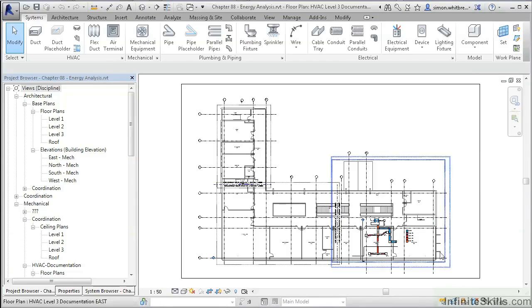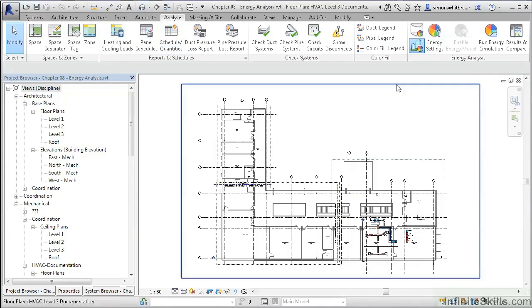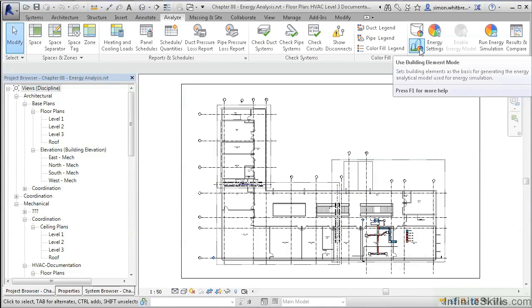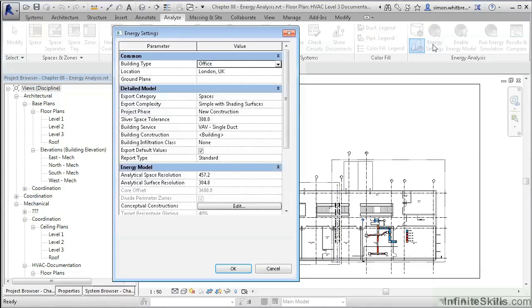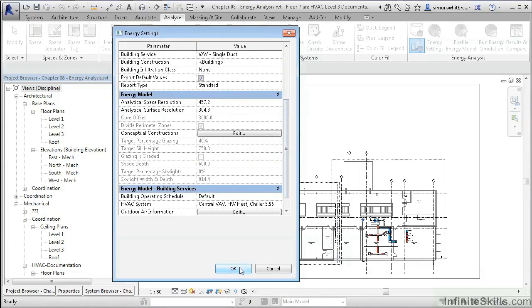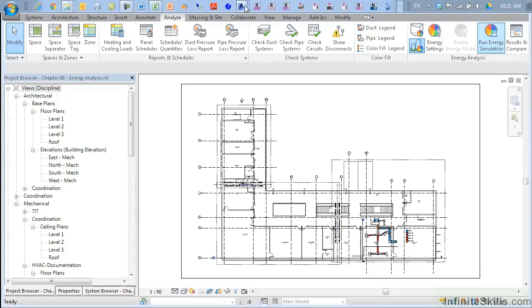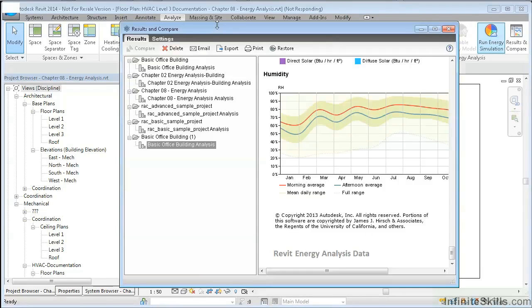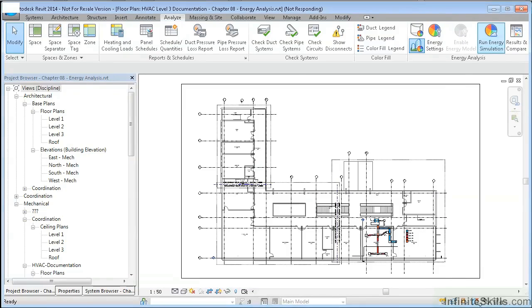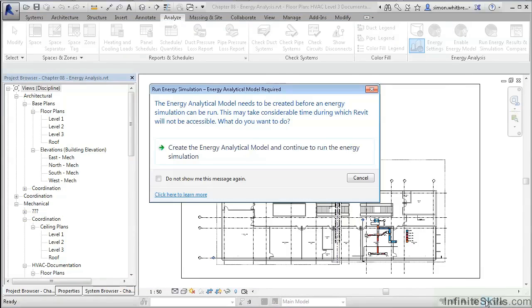Another method for performing this analysis is to use the Building Element Mode. This functionality is new to Revit MEP 2014. We can select the energy settings as before and run the energy simulation. Running this, though, does require considerable processing power. The energy analytical model needs to be created and it may take considerable time — this of course depends on the complexity of your project.